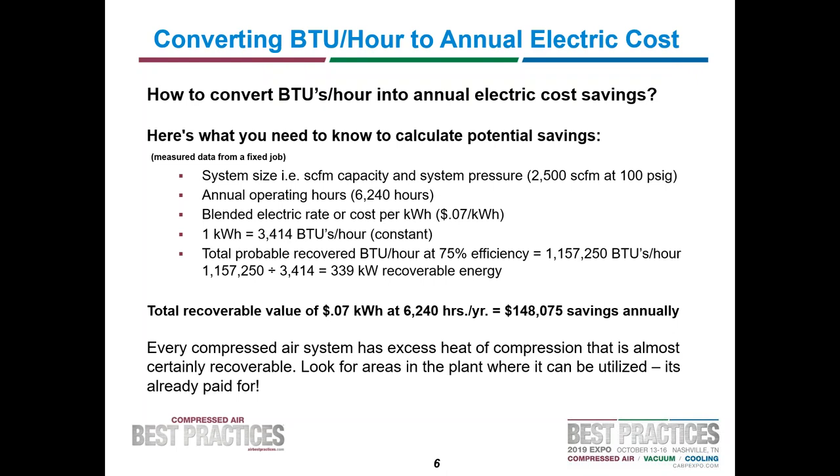One KWH is 3,414 BTUs per hour — that's a constant. The probable recovered BTUs per hour at 75% efficiency: 1,157,250 BTUs per hour divided by 3,414 equals 339 KW. At 7 cents per KWH, that's $148,000 a year in savings. Every compressed air system has excess heat of compression, and it's recoverable. Look for places in the plant where it can be utilized, because it's already paid for.